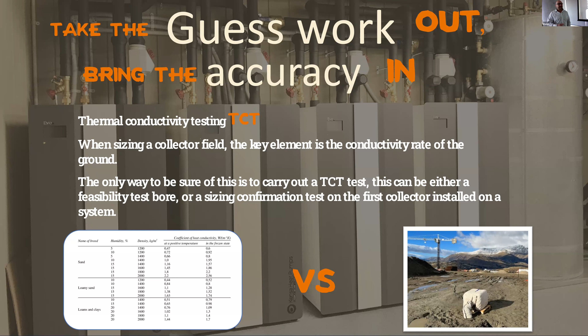That can either be after the design, once you've already confirmed you're definitely doing ground source, where you do a test on the first loop while the others are being drilled, because then we can add loops or take loops away. Normally we're actually taking away rather than adding. Or you do it as a standalone test as part of a feasibility.